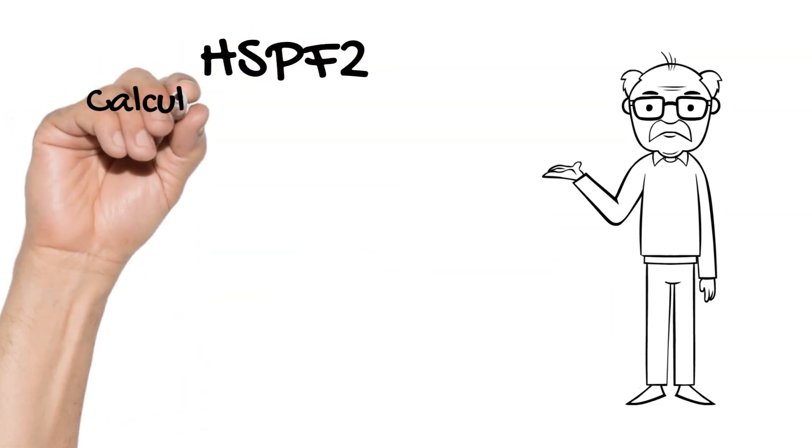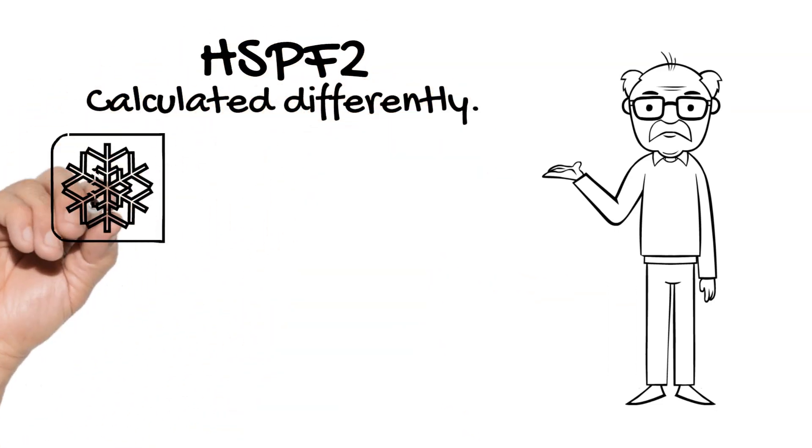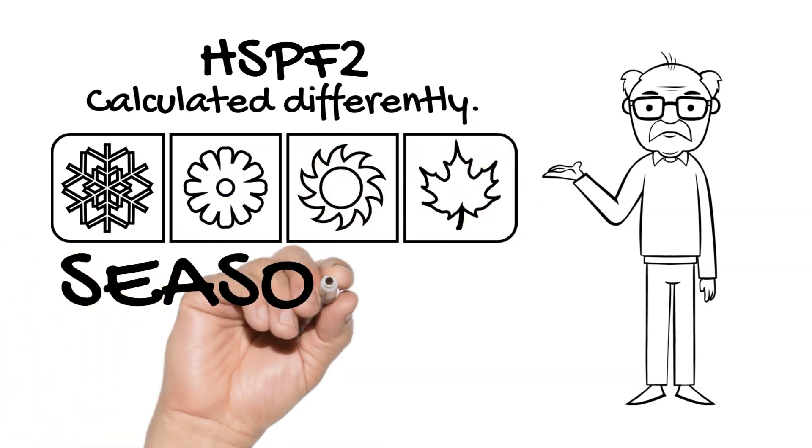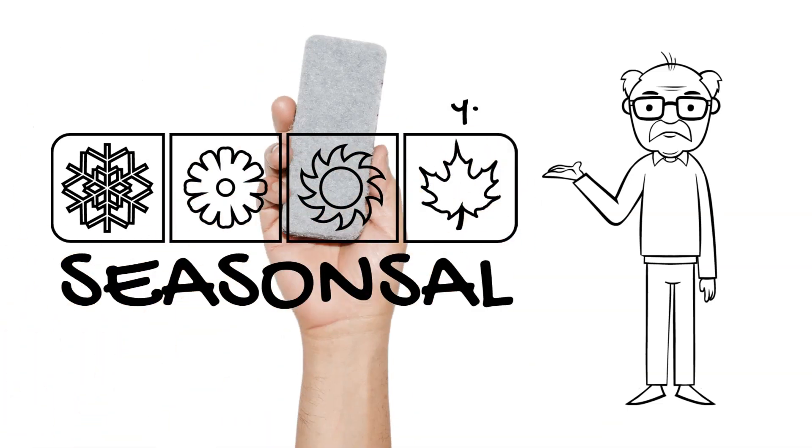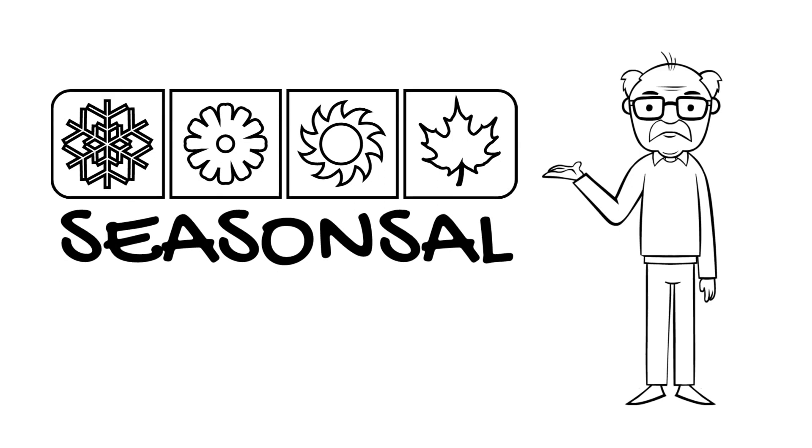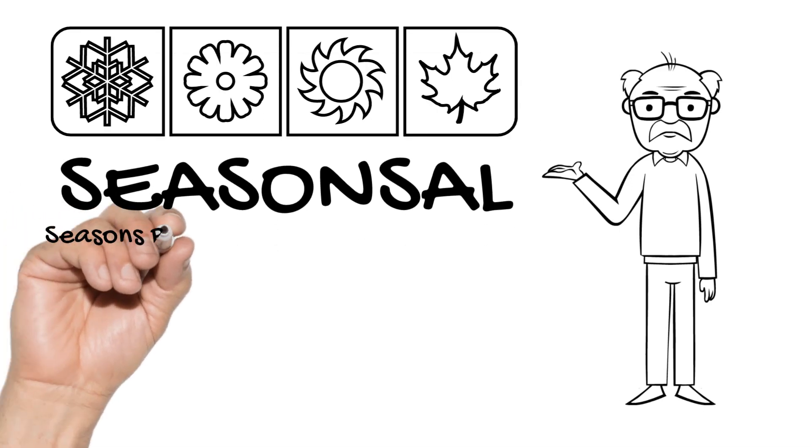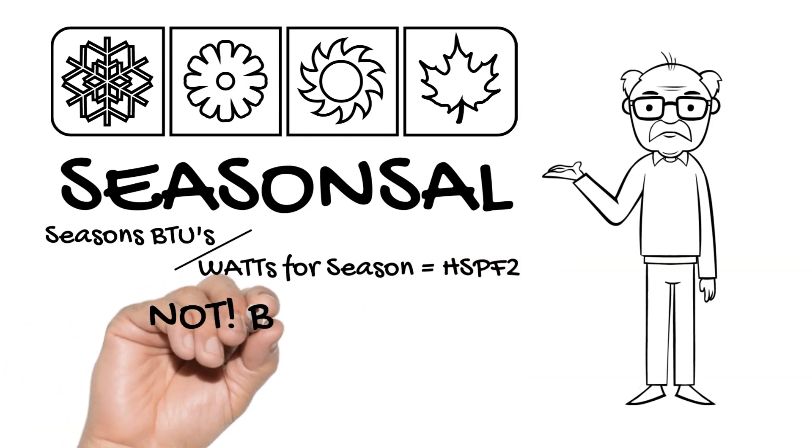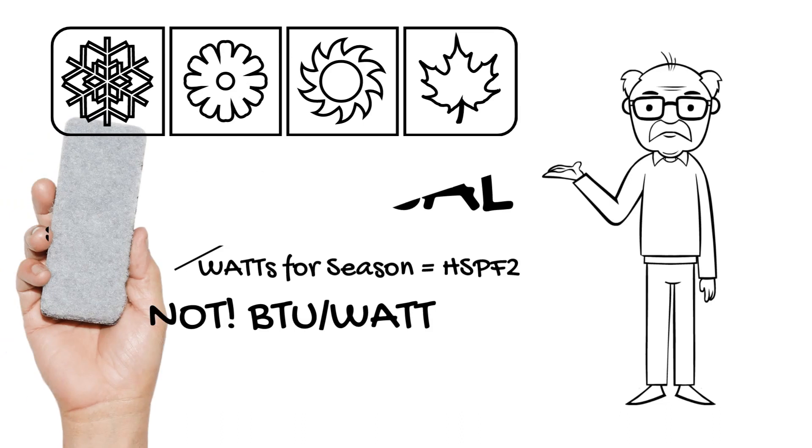HSPF2 is calculated different than cooling. It stands for heating seasonal performance factor. The key difference is seasonal. The total season's heating BTUs are divided by the season's total watts consumed producing that heat. It is not a straight BTU per watt calculation.